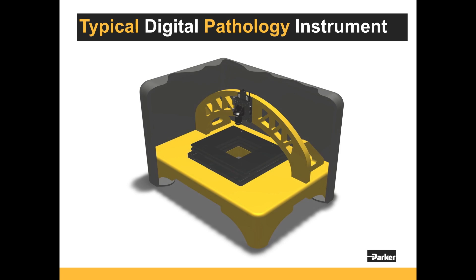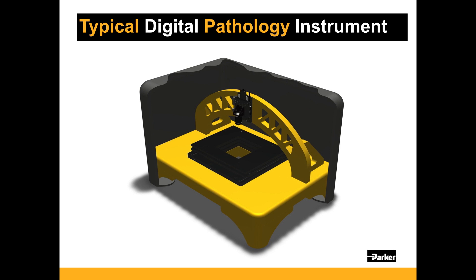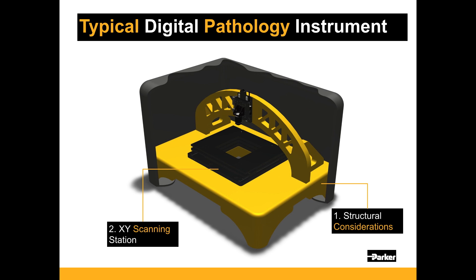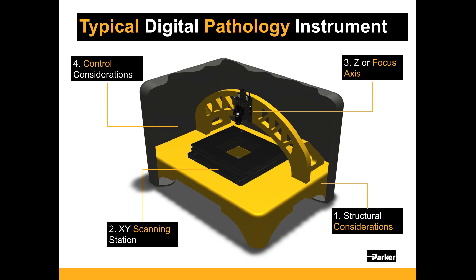A typical digital pathology instrument usually requires key design consideration around four key elements: first, a strong, stable structure; an X-Y scanning stage; a focusing or Z-axis stage; and lastly, a high-performance control.